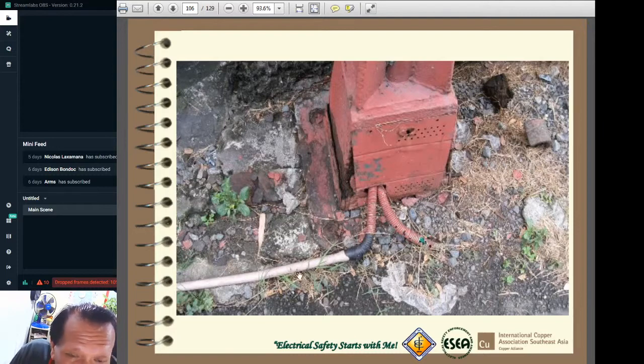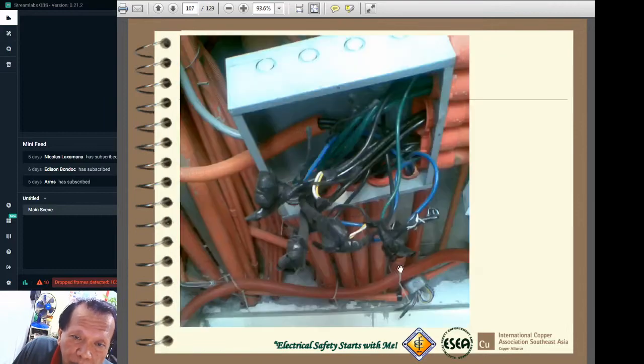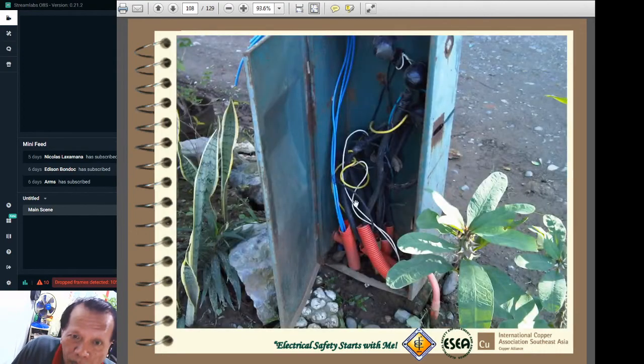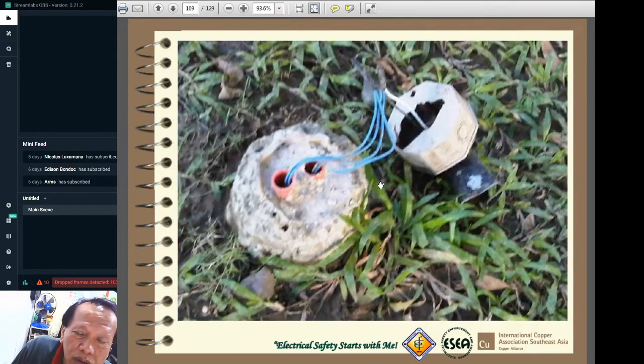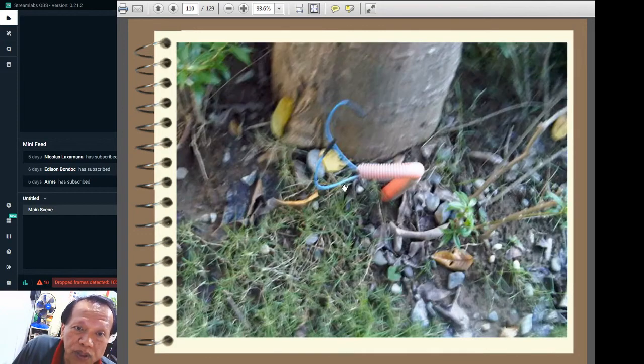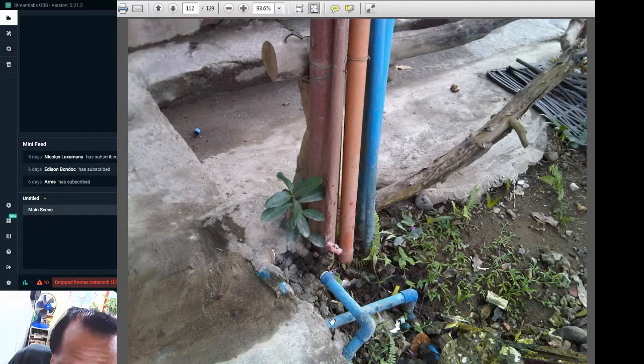PVC should use the rigid PVC and should be embedded in concrete, with a minimum of 6 inches cover of concrete. And so with this, the installer did not put all the splices inside and provide a cover, so that they wouldn't be exposed to the weather and to danger. So with this, no proper splicing or mechanical protection of the wires. This one also, and this one also. The electrician made a mistake of combining the use of, I think, electrical conduit with water pipe, which is improper.